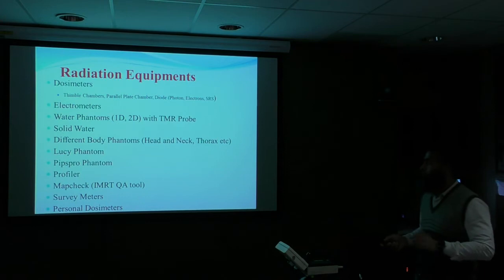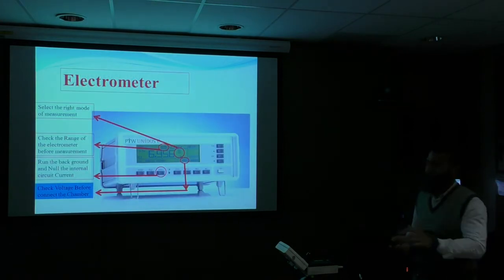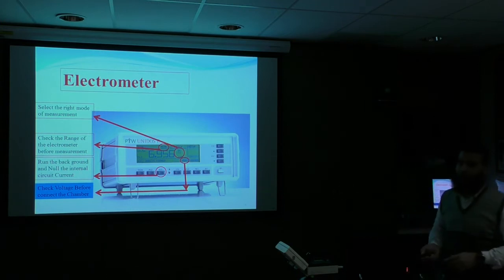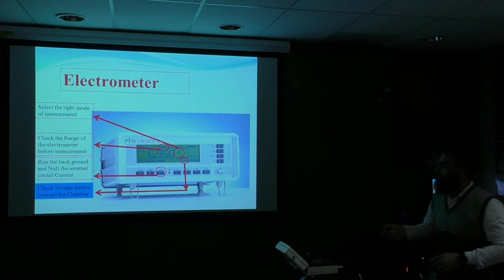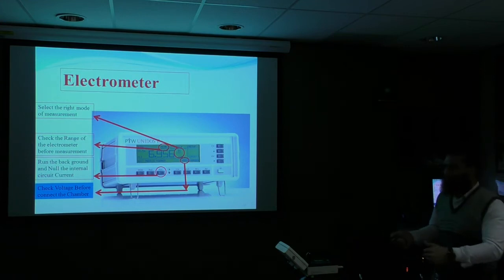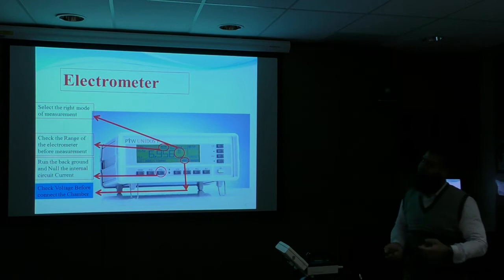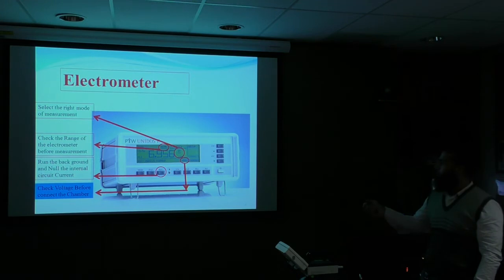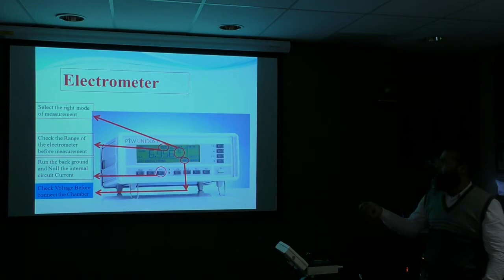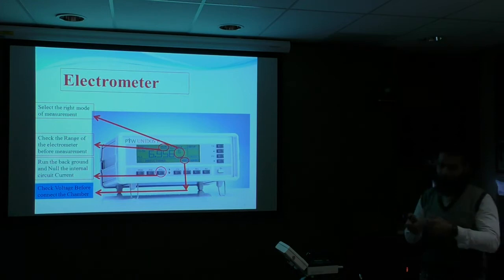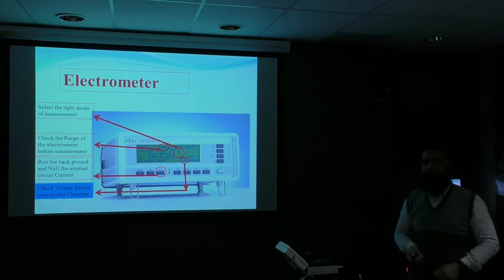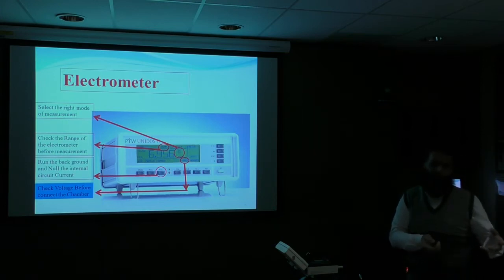Hopefully this will help you a little bit. So this is the first thing - when you go for dosimetry, one of the important things you need to know about is the electrometers. Whenever you switch on the electrometer, before you connect the chamber, you should check all these things. You have to select the right mode, then check the range of the electrometer, because if you don't select the right range it will overload, and overload is not good for the electrometer.